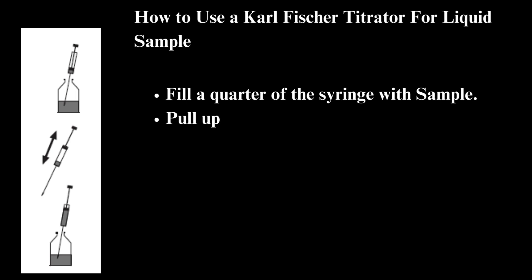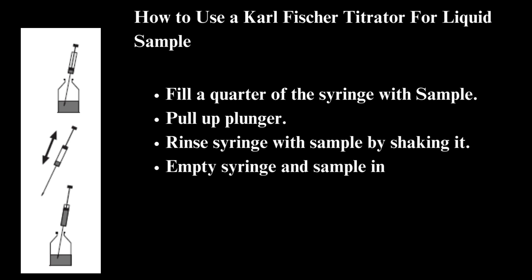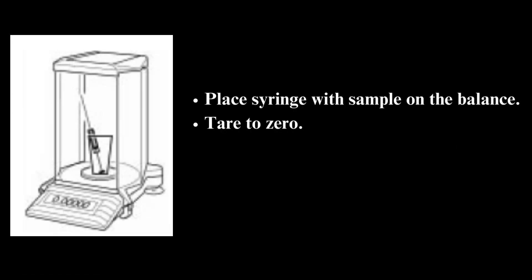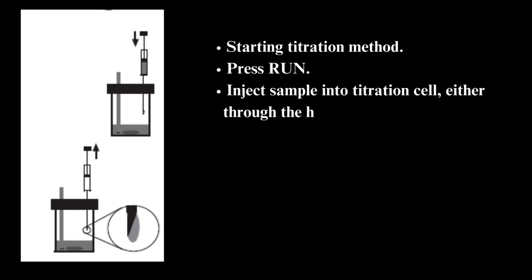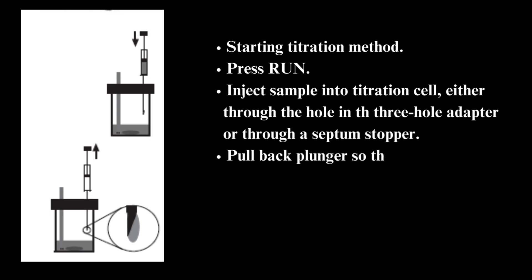How to use a Karl Fischer titrator for a liquid sample: fill a quarter of the syringe with sample, pull up the plunger, and rinse the syringe by shaking it. Empty the syringe and sample into the waste bottle. Fill the syringe with sample and wipe the needle with a paper towel. Place the syringe on the balance and tear to zero. Start the titration method, press run, and inject the sample into the titration cell — either through the hole in the three-hole adapter or through a septum stopper.